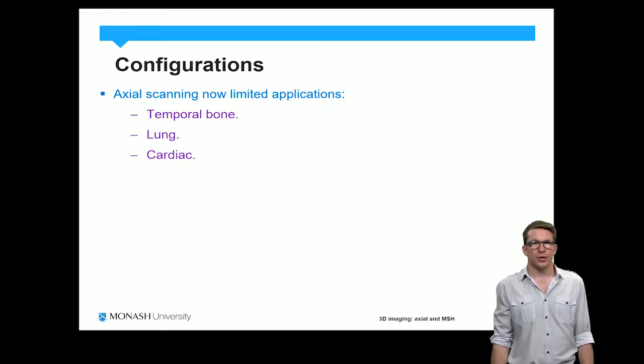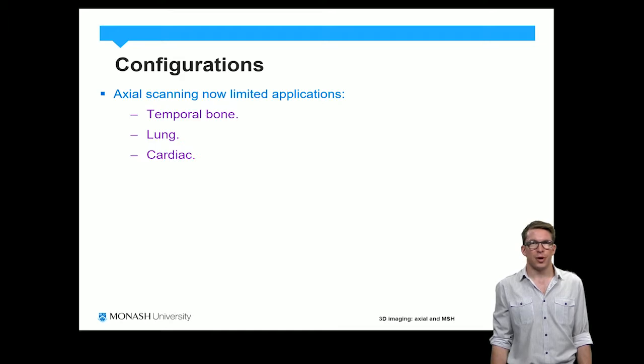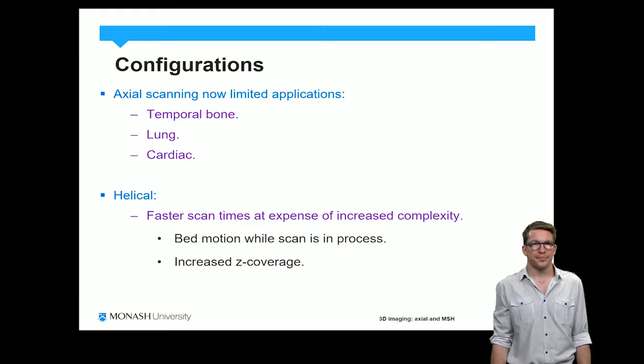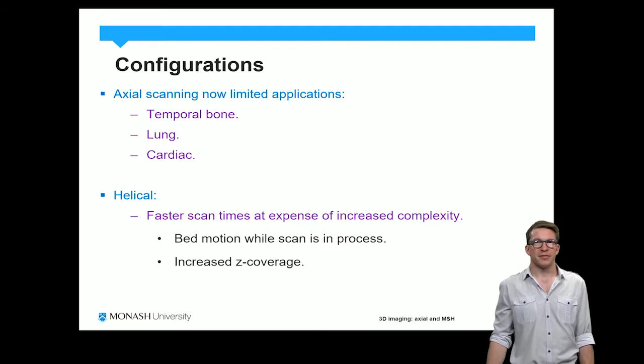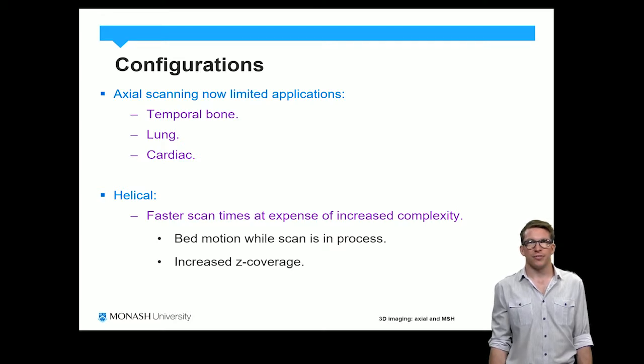Axial scanning is used sometimes in limited applications but has largely been superseded by helical scanning. Some of the axial applications include scanning of the temporal bones, the lungs, and also cardiac gated CT. Helical scanning has significant benefits in terms of being faster and increased flexibility, but there is a level of increased complexity because we have to do some re-binning of the data before we can do the reconstruction. Helical scanning relies on the fact that the bed moves whilst the scan is in progress.